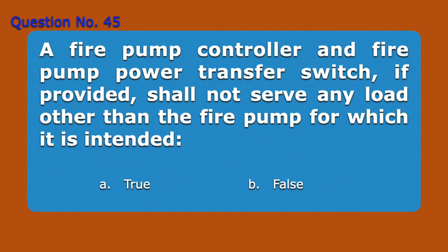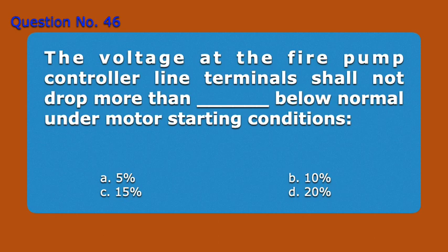Question number 45. A fire pump controller and fire pump power transfer switch, if provided, shall not serve any load other than the fire pump for which it is intended. A. True. B. False. Answer A. True.